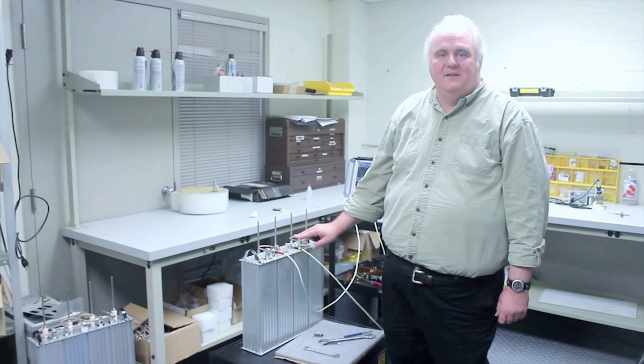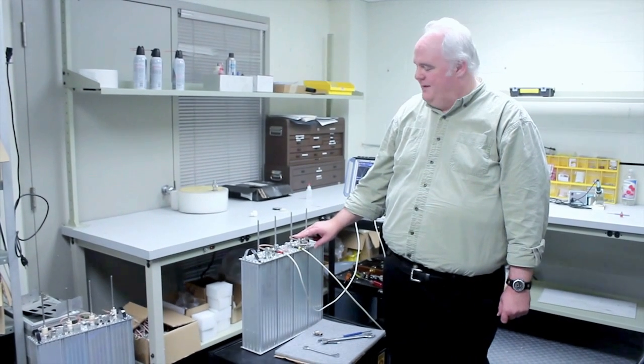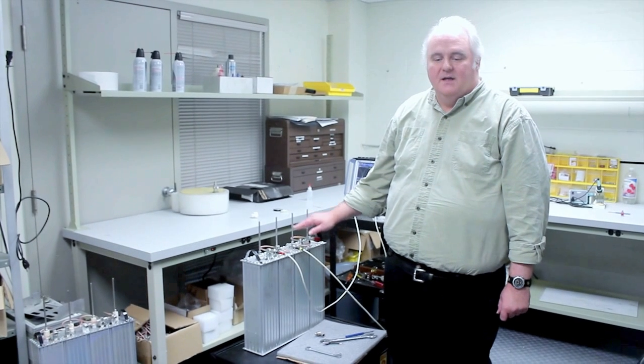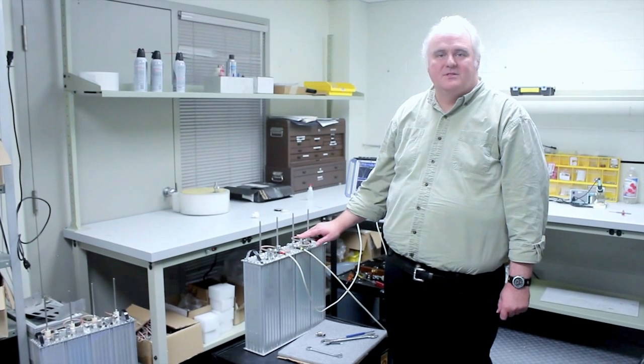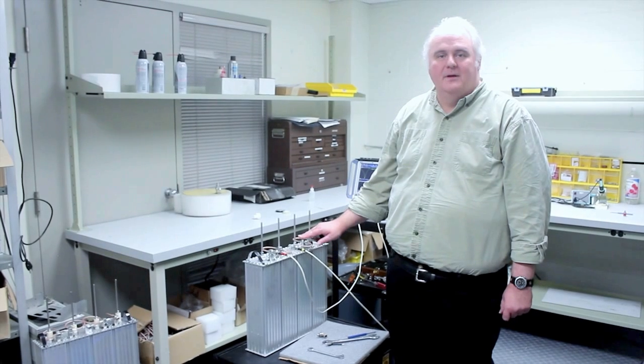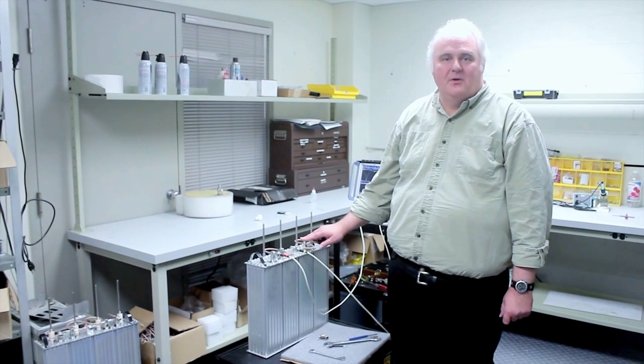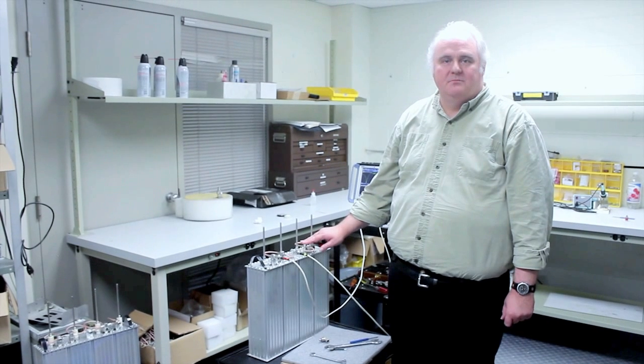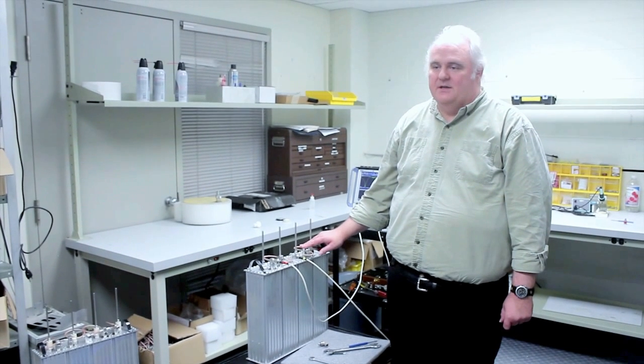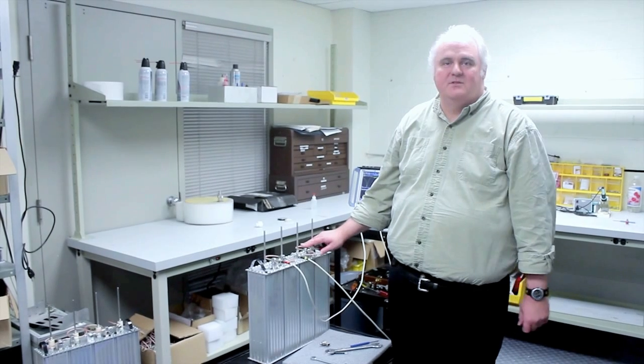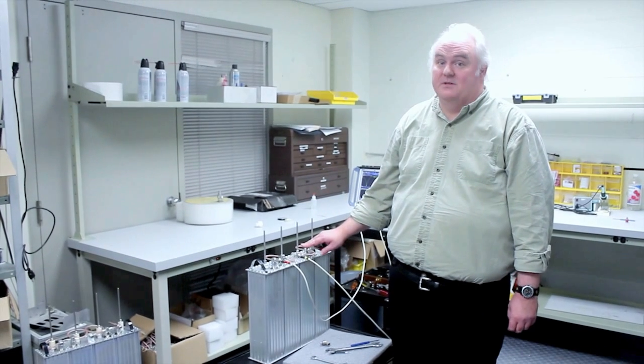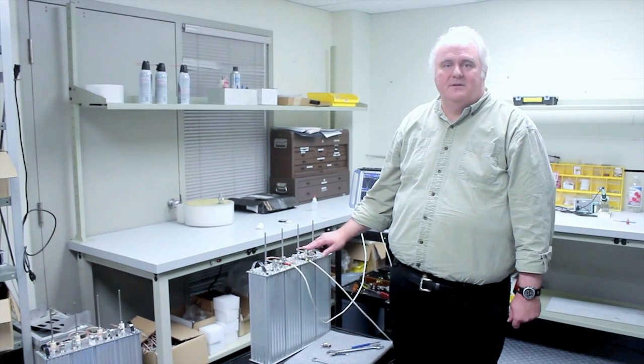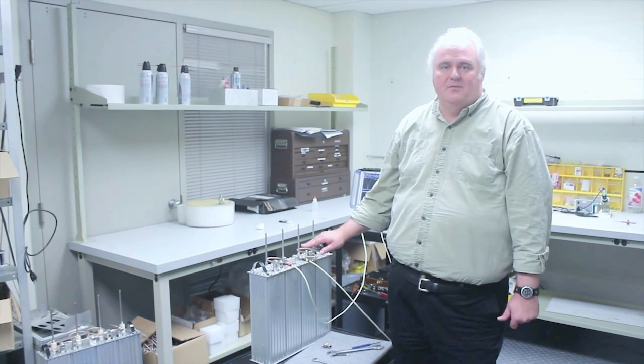As an important safety tip for those of you out there who may wish to tune the duplexer with something other than a network analyzer, it's important that your signal source be low power. Do not try and tune this under transmit power as it could cause high reflection, possibly damaging your transmitter. And if you're swapping cables while it's under transmit power, it could possibly cause injury. So remember when tuning the duplexer, do not tune it under transmit level powers.